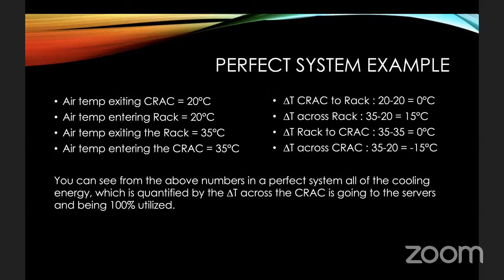So in a perfect system, the air temperature exiting the CRAC would be, in our example, 20 degrees. The air entering the rack would be 20 degrees. The air exiting the rack would be 35, and the air entering the CRAC would be 35. That means that our delta T from the CRAC to the rack is zero, because it's 20 degrees coming out of the cooling system and it's 20 degrees entering the rack. That means 100% of our cooling energy that is being sent out by the CRAC is reaching the rack.